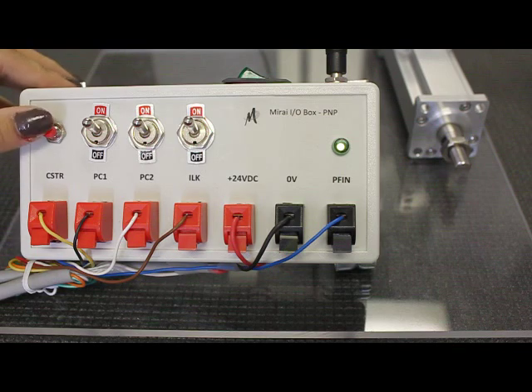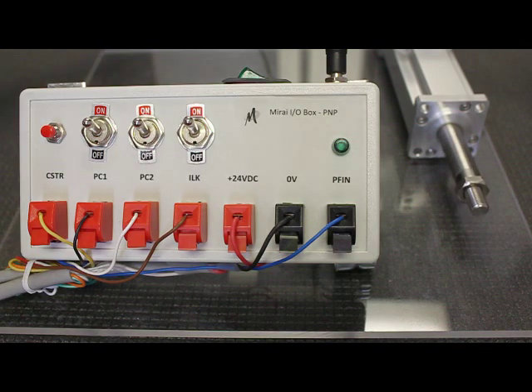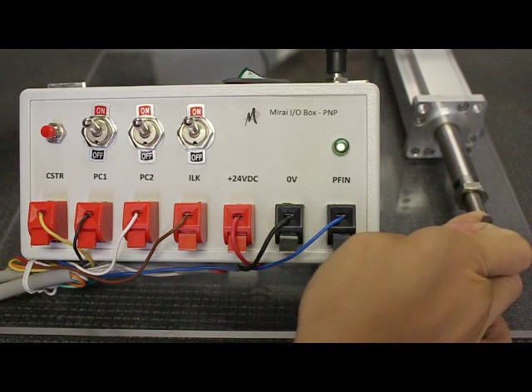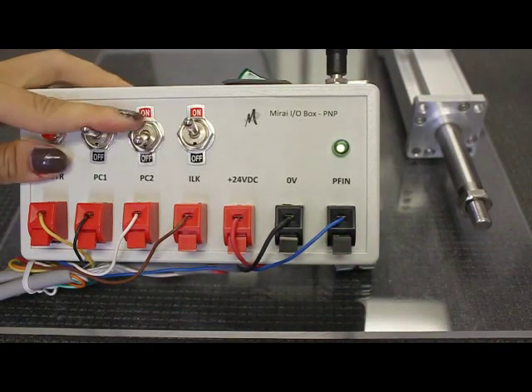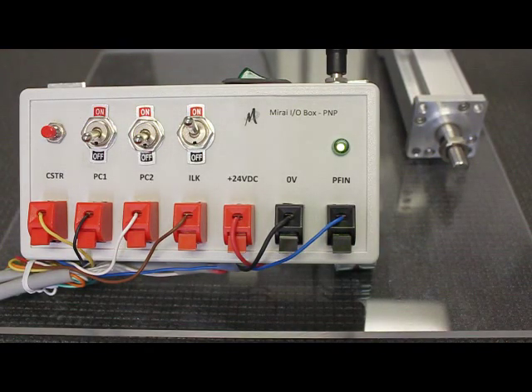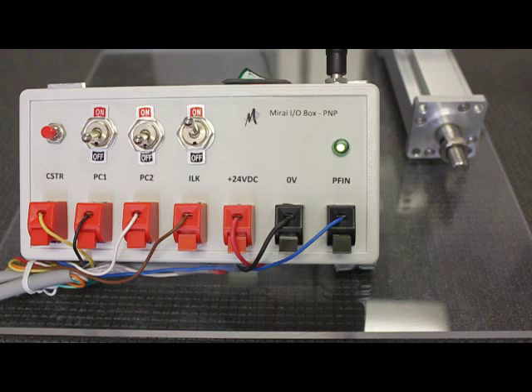Move 3 is set to a force controlled move so that it will move at high speed to an approach point and then move slowly until it encounters the target force. The actuator pushes continuously until another move is commanded. In this case we will command move 0 to bring the actuator back out of force controlled mode.